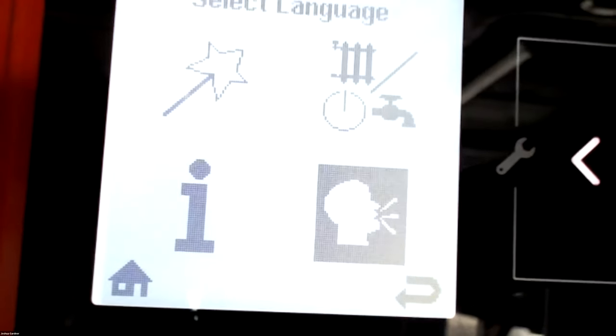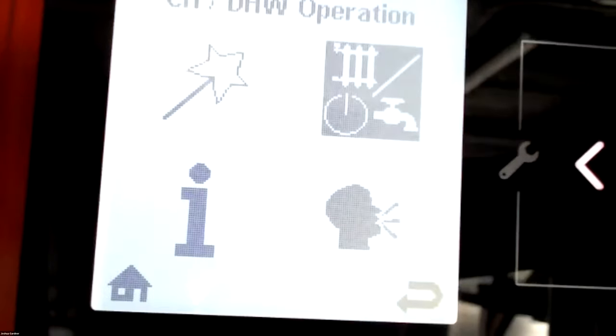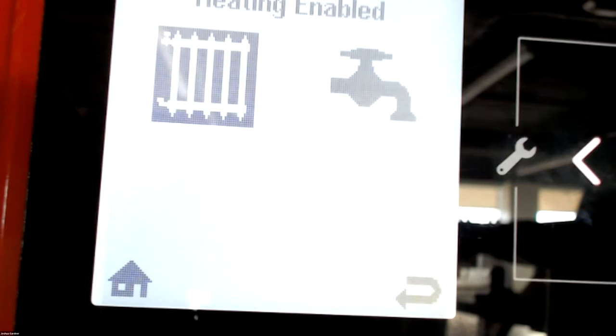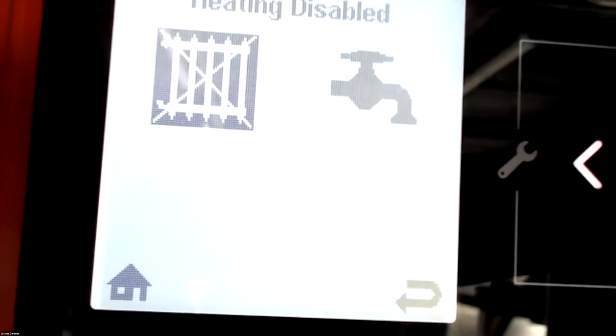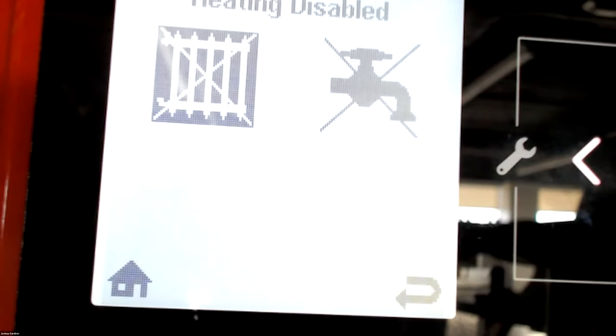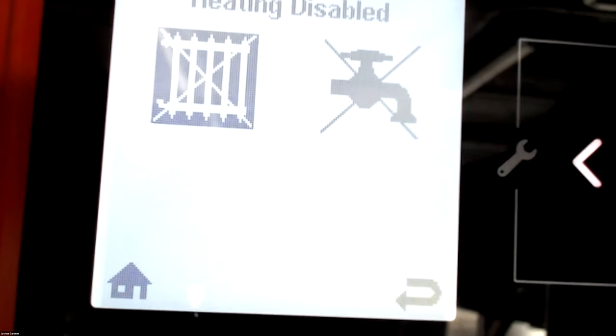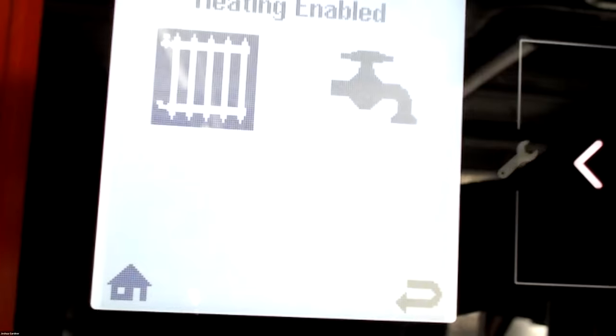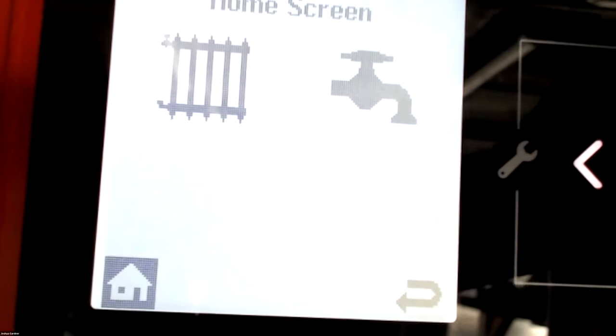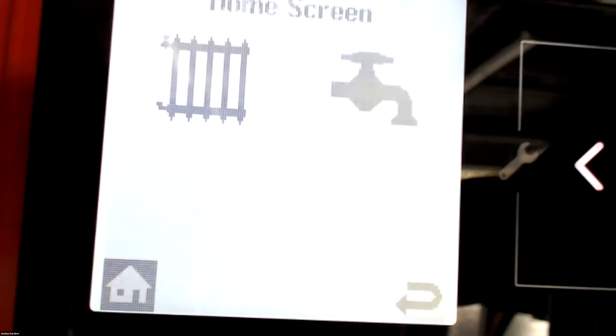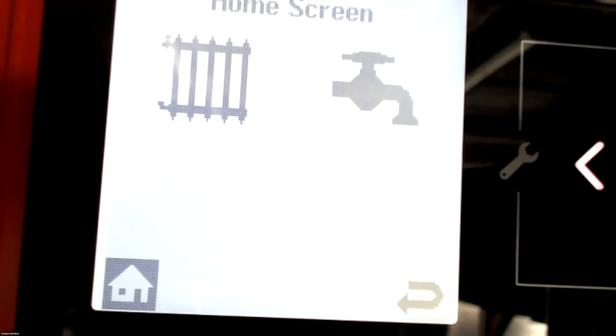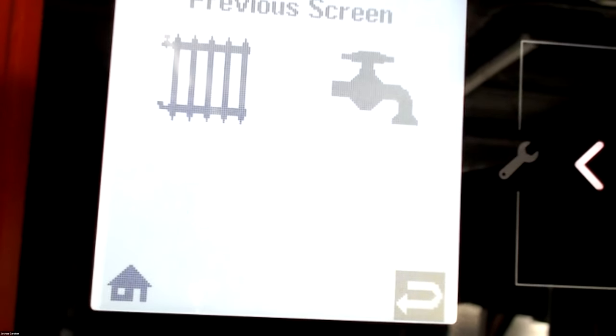So we'll start up here at your CH DHW operation. This just allows you to turn the space heating off and your domestic off. So if you were doing something, you didn't want the boiler to come on and run, you could turn those off. Or if you had a combi, you want to turn the domestic off so it doesn't come on, you could do that. So this just gives you a quick reference to turn those things on and off. And then if you always go back to down here in the lower left, you can always go back to the home screen. And then this little arrow right here just takes you back one screen.